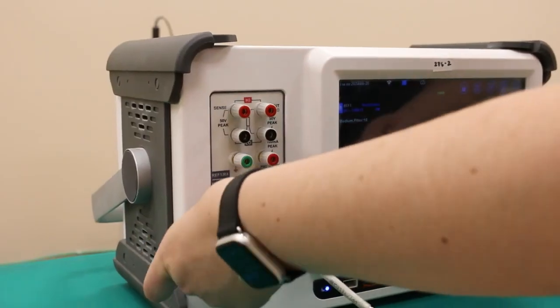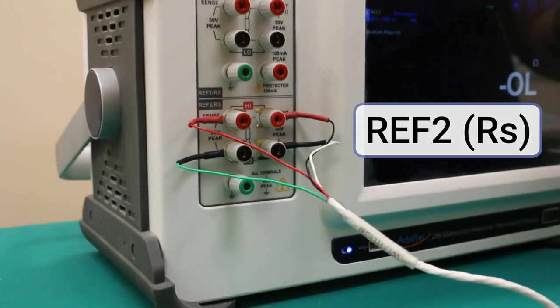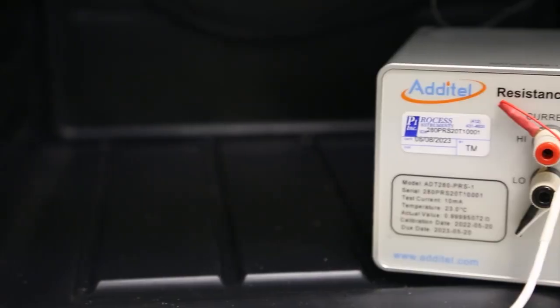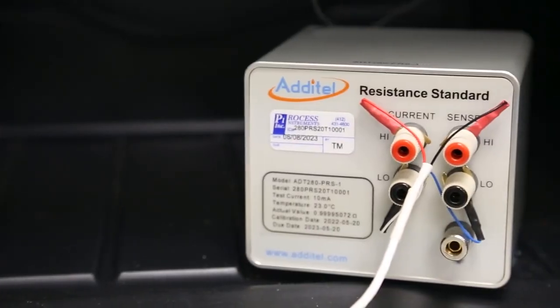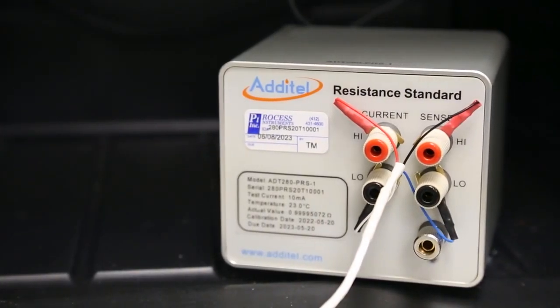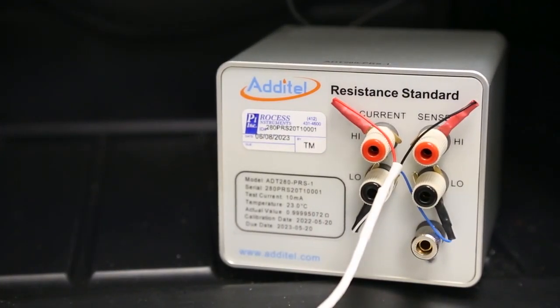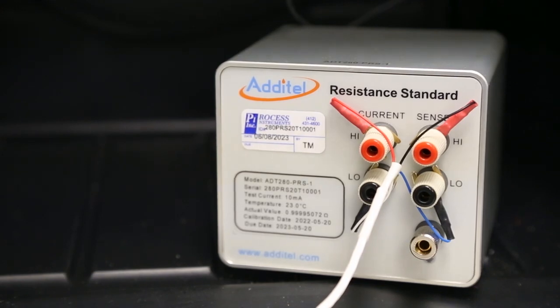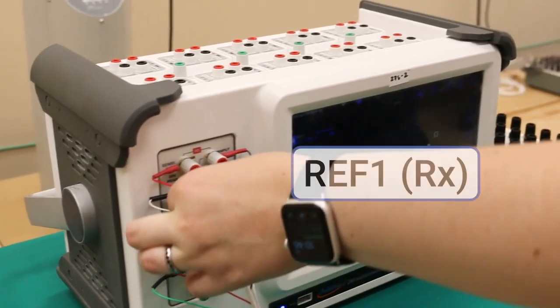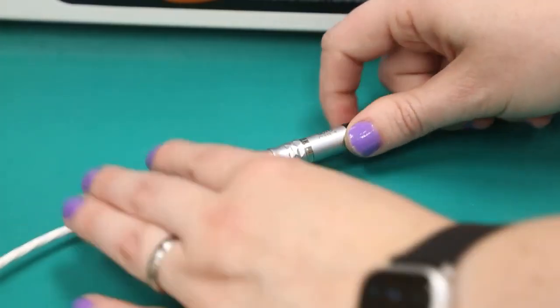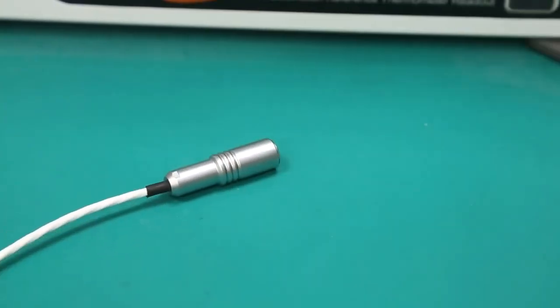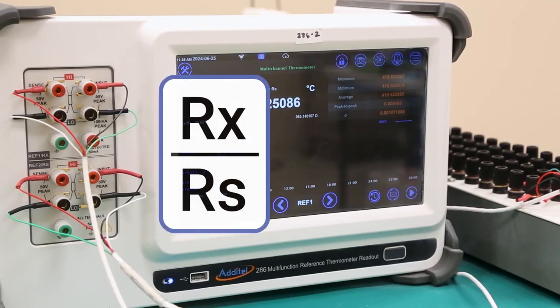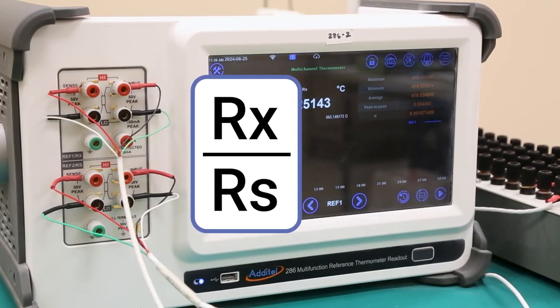To begin, we'll connect a reference standard resistor to the REF2 port on the 286. This 100 ohm resistor is stored in a precision temperature bath held at 23 degrees Celsius and will be used as an external reference to calibrate the 5 probes against. Next, we'll connect a 4-wire cable to REF1. Since all the DUT probes being used have the same quick connector, we will be able to easily swap them out without disconnecting the 4-wire connection. While in bridge mode, the 286 will measure the resistance ratio from both reference ports.